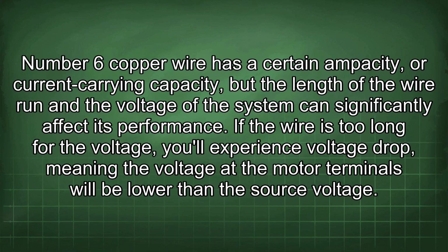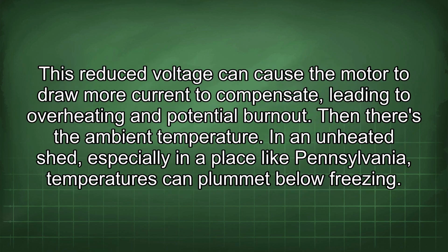Number 6 copper wire has a certain ampacity, or current carrying capacity, but the length of the wire run and the voltage of the system can significantly affect its performance. If the wire is too long for the voltage, you'll experience voltage drop, meaning the voltage at the motor terminals will be lower than the source voltage. This reduced voltage can cause the motor to draw more current to compensate, leading to overheating and potential burnout.